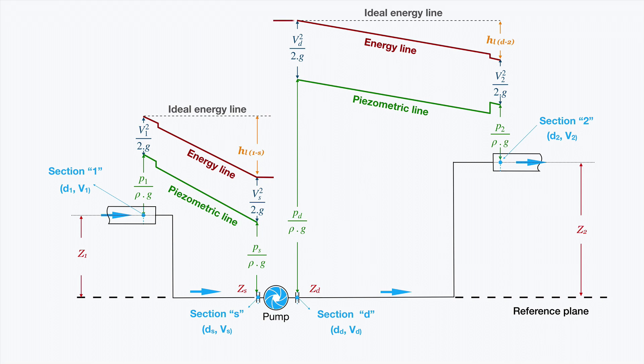This is the energy level we need at section D to transport the fluid from this section to section 2. There is a gap — a lack of energy — that I'm representing here. So we need to add this amount of energy to the system. Who is responsible? The pump. This amount of energy needed by the system is the amount of energy the pump should provide, and this is the pump head — H, HP, or TDH. It can be called in different ways, but the right name is the pump head.